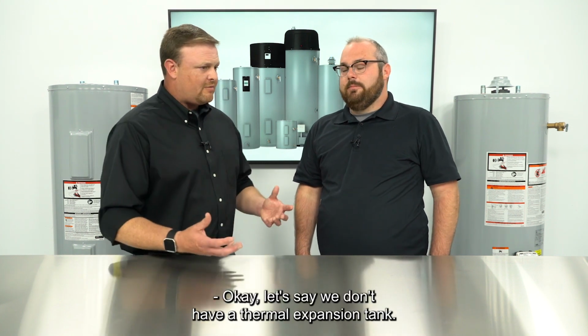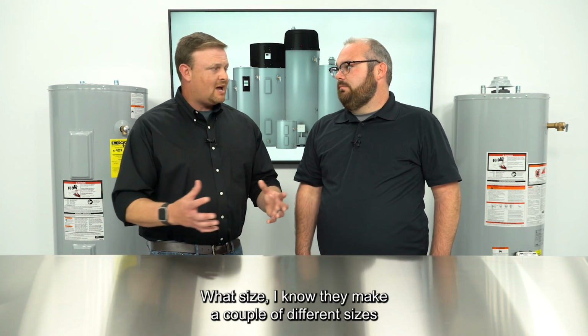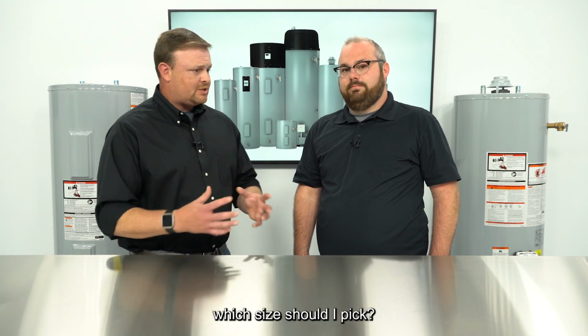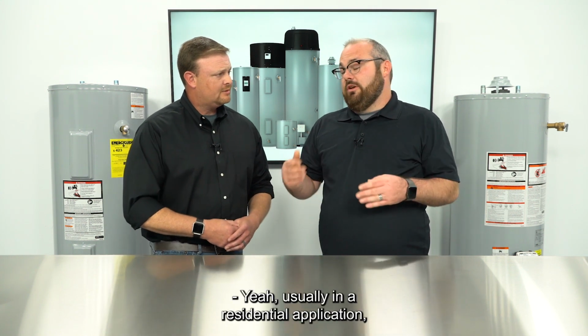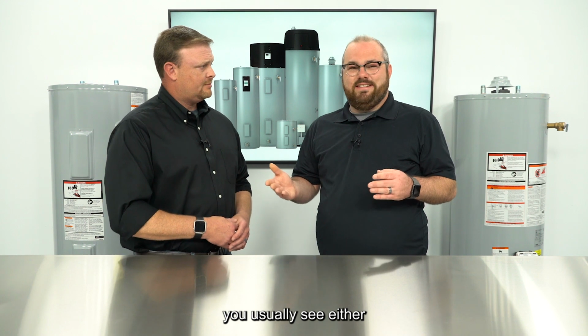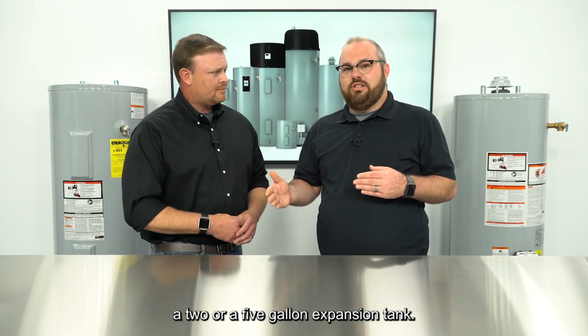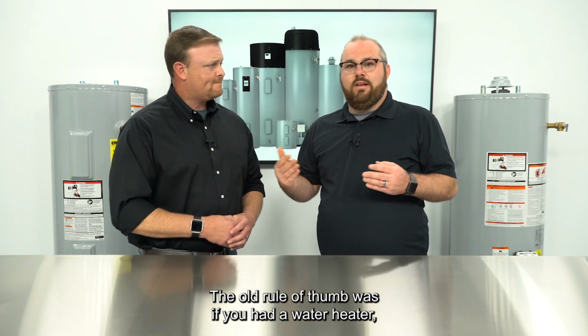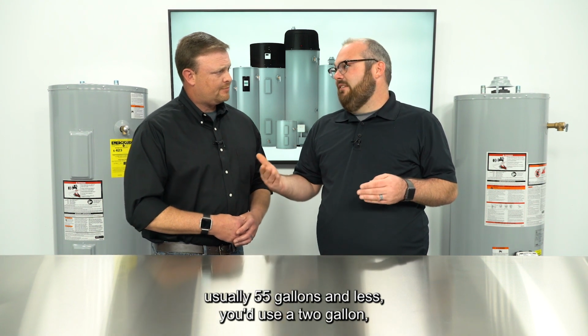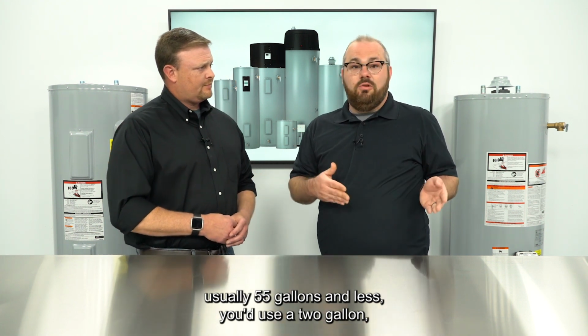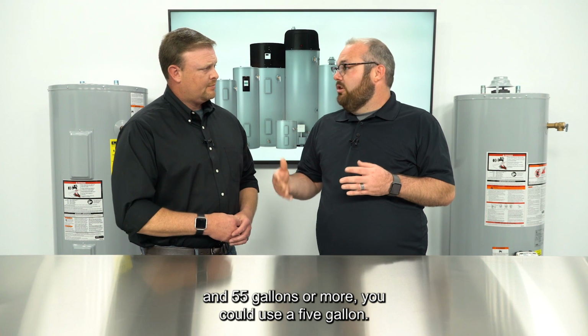Okay, well, let's say we don't have a thermal expansion tank. I know they make a couple of different sizes. Which size should I pick? Usually in a residential application, you see either a 2 or a 5-gallon expansion tank. The old rule of thumb was if you had a water heater of 55 gallons or less, you'd use a 2-gallon, and for 55 gallons or more, you could use a 5-gallon.